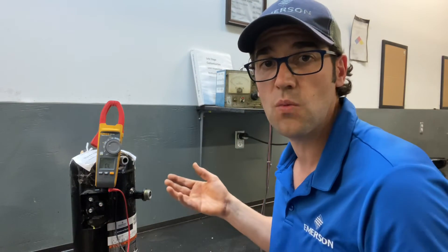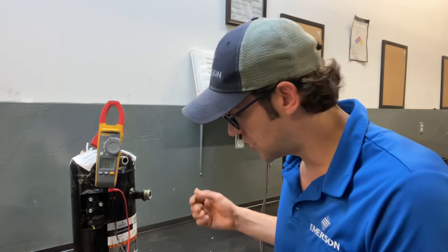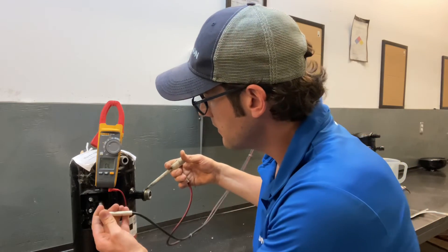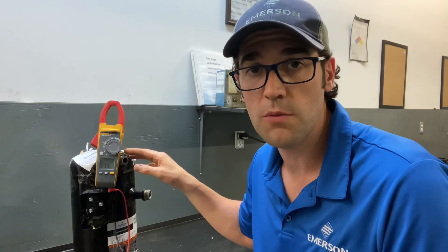This is telling me this compressor winding is good, but this compressor only ran for five days in the field. And I check it with a high pot test. What a high pot is, is checking the leakage of those windings, and it instantly fails. So there are bad windings in this compressor. Sometimes you'll check it with your meter and it will say it's good, but when you go to do a megohmmeter test, it fails that. It has a bad winding, so just be aware of that.